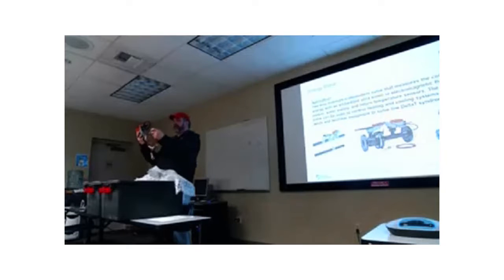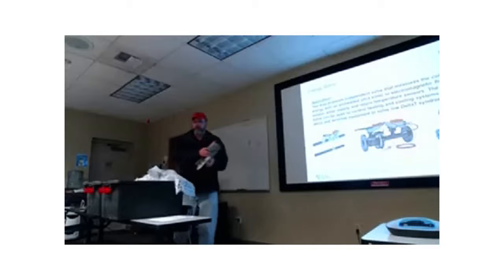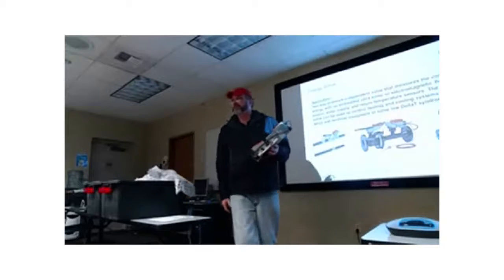This is our littlest energy valve. In this case, we have two NPT connections for the pipe because we want to make sure that well is good, so you don't have to put a weldolet in. You can basically just screw these into the pipe. And then here's the flow meter, there's the valve. And if you want to dump the data out of the valve, you have this little Cat5 connection. You can hook it up to your PC and dump it right out. It actually stores 12 months worth of data. Yeah, 12 months, 13 months.